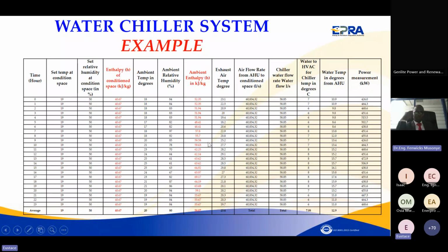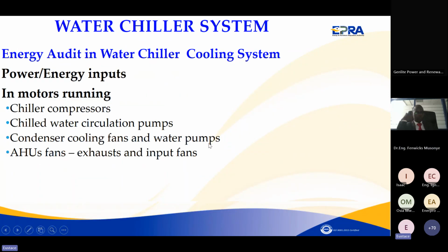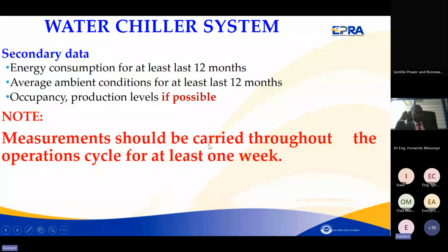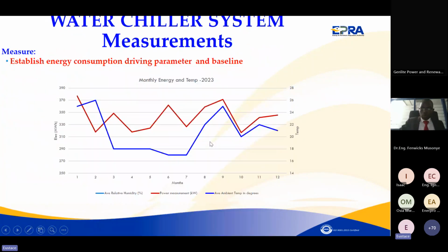So whenever you see something funny happening - that is why we said you need to establish the cooling load. What are the drivers of energy consumption in a chiller system? It's not the temperature alone; also the relative humidity of the place drives the energy consumption.